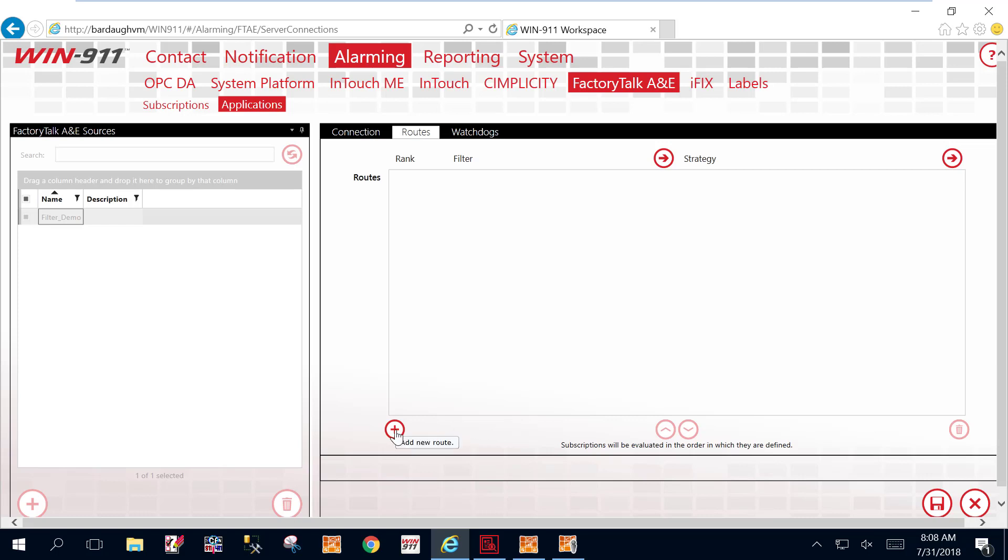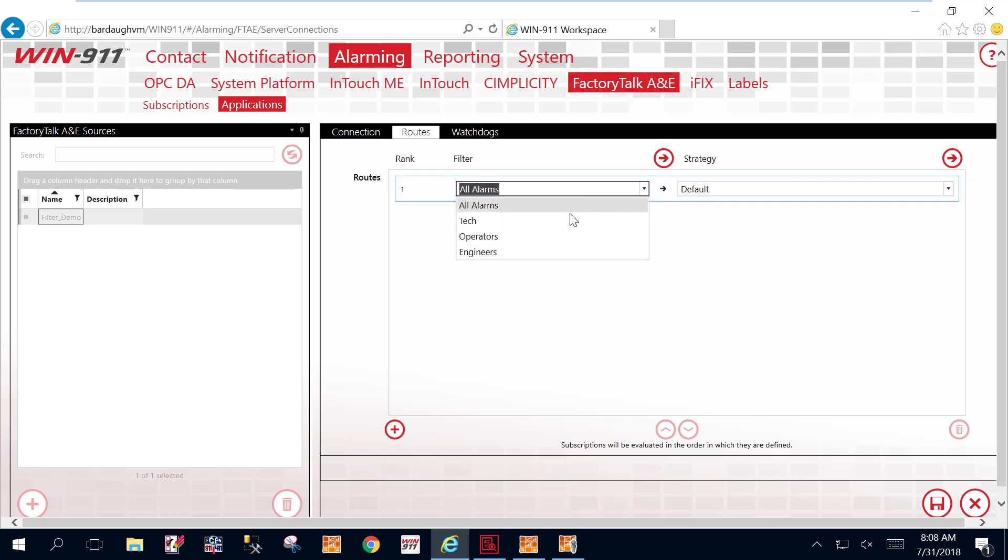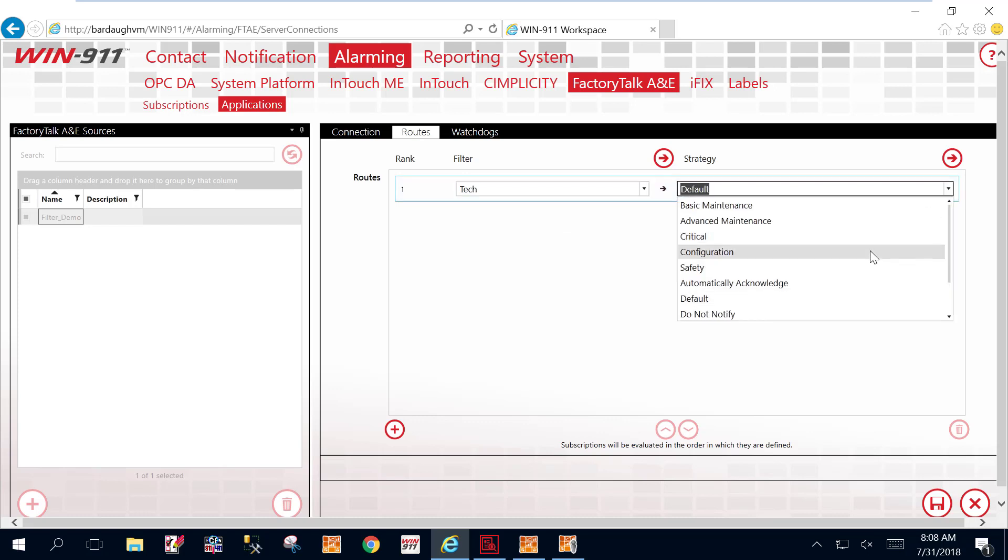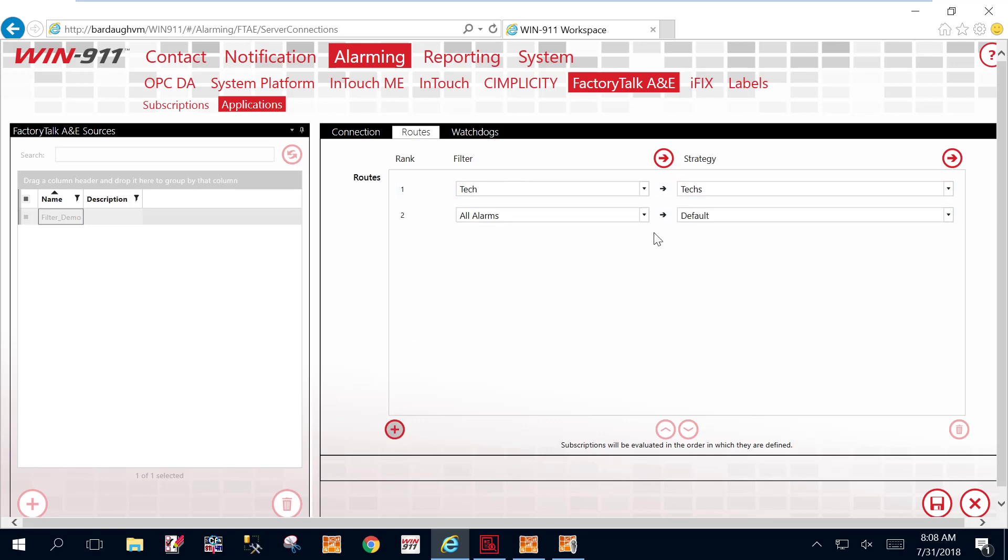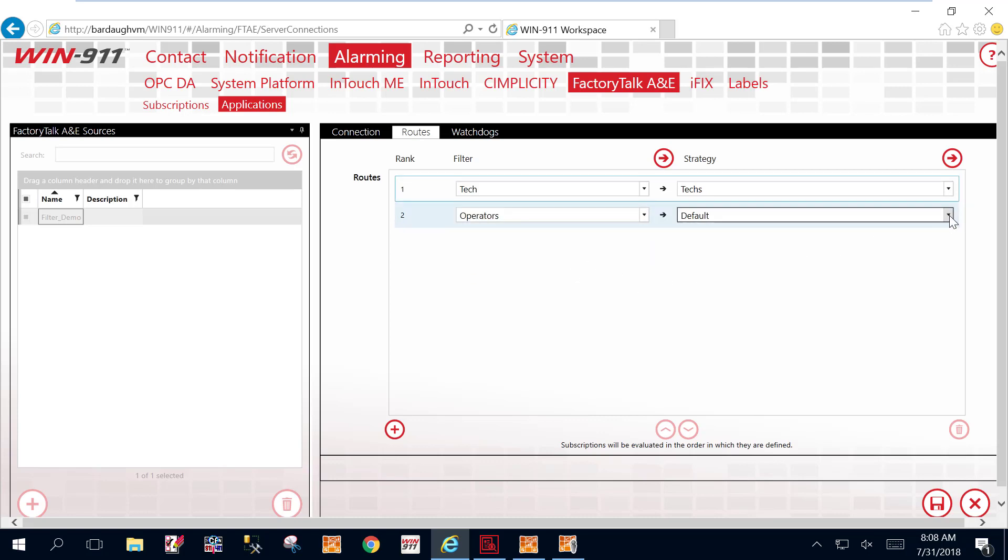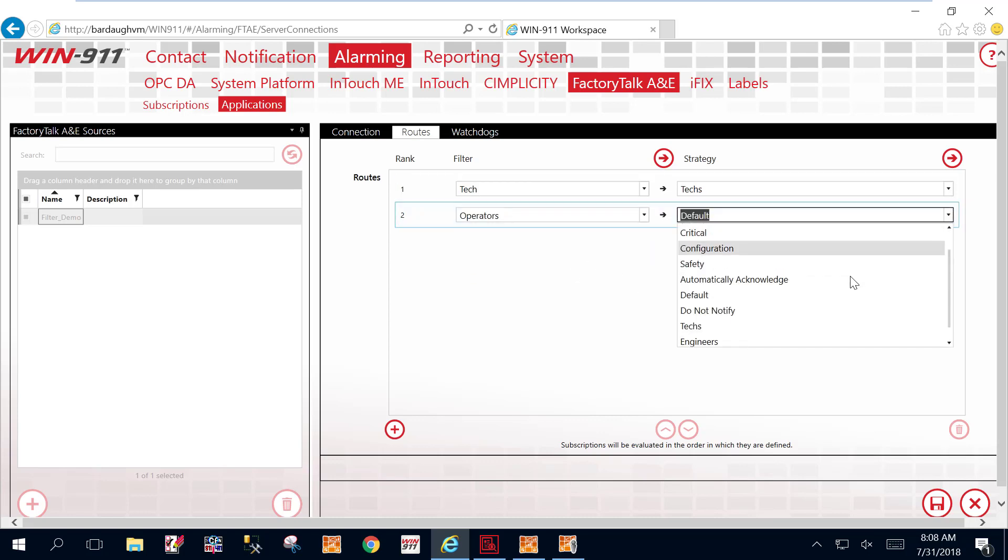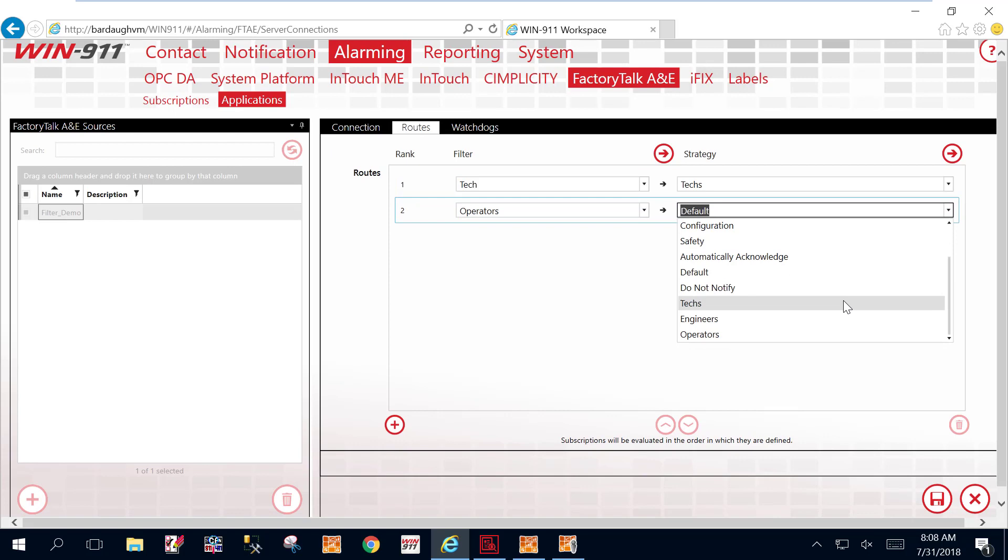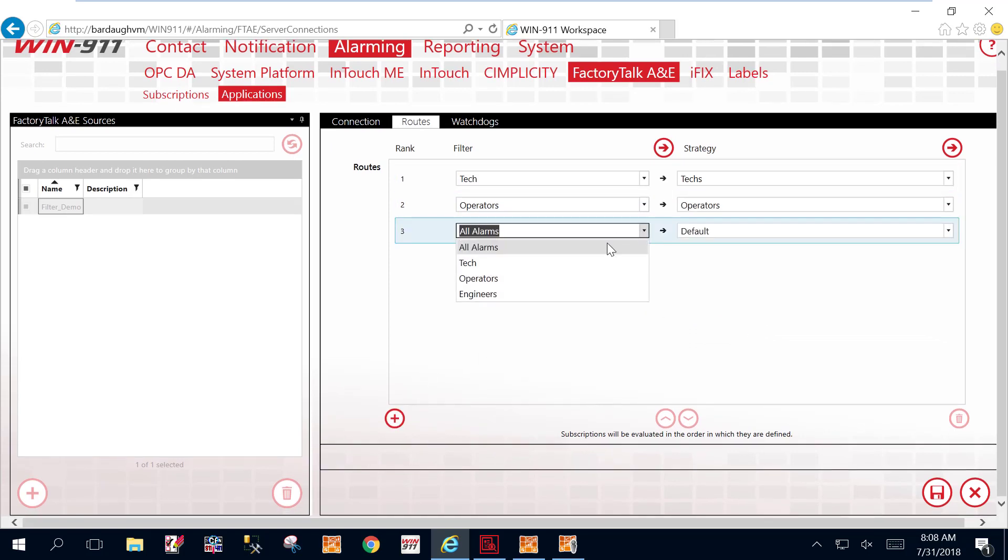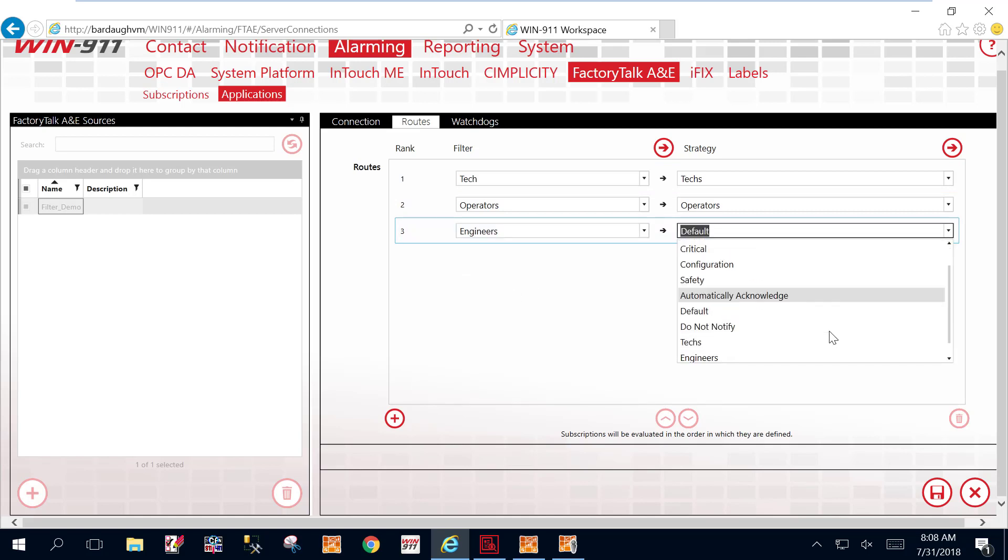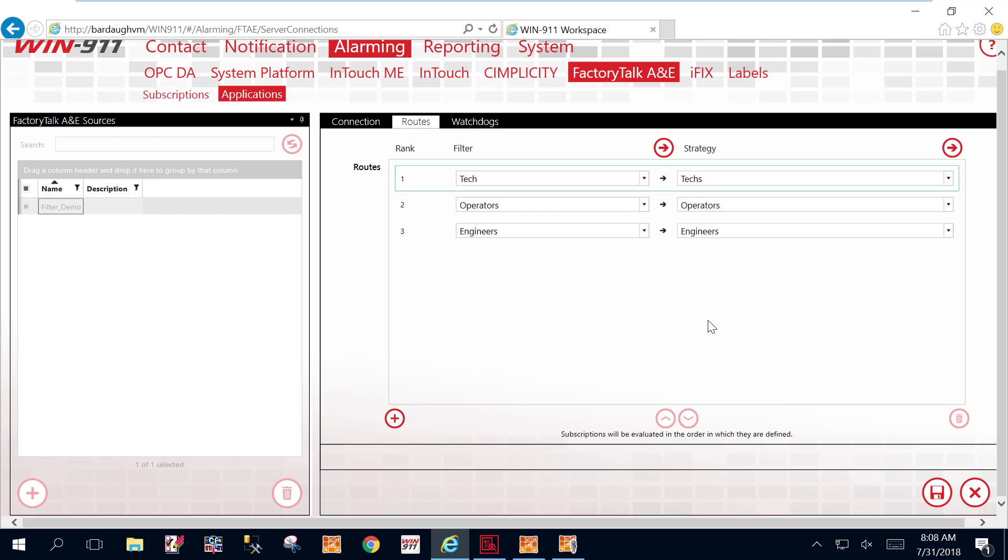We're going to add a new route. And the first route, those drive alarms, those technician alarms that have the drives, those we called tech, we're going to point them to a strategy. And I have a strategy over here that is named tech. So your filter or alarms we just made is going to point to some strategy. That's where it's going to point to your call list of people. I'm just going to go online and do the same thing for the operators. And these are going to point to a strategy that I also have called operators. Finally, we're going to make our filter for our engineers that we just added. That's the severity filter. And we're going to point that to some strategy I have called engineers. And we'll save that.